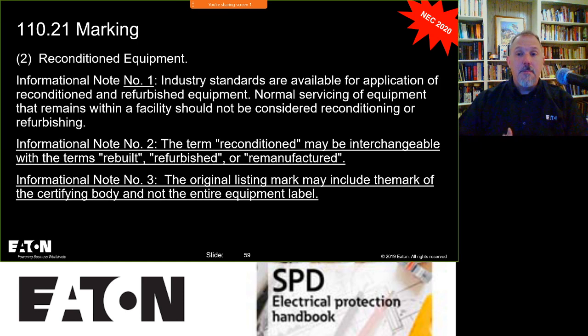That's another big misconception - when you say remove the listing mark, they'll say the listing mark is part of my manufacturing label. That doesn't mean you take the whole label off - you just obliterate or get rid of the listing mark. Now in some cases the listing mark may be part of the plastic or thermoset body of the product, etched in there. The only way to remove that would be to cross it out in some form or fashion. You don't want to ruin the integrity of the product - don't create a problem trying to take something off. That's another important thing to remember.